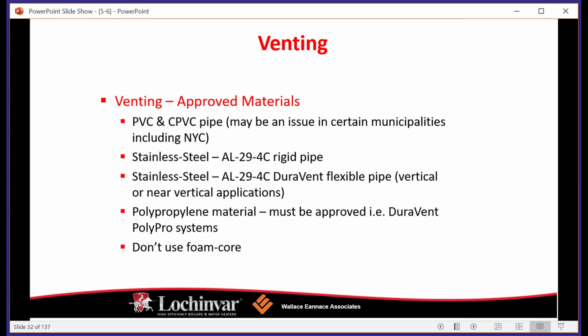So earlier in some of the slides, we discussed that venting is more flexible for a condensing boiler. So on a condensing boiler, you have the list of approved materials as PVC, CPVC, stainless steel AL29-4C, rigid or flex, and polypropylene. The reason why we are so much more competitive with PVC is the condensing technology, okay?